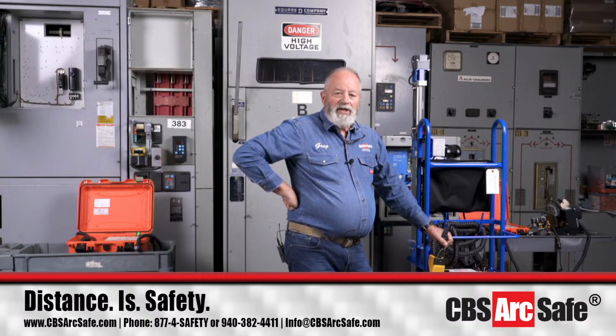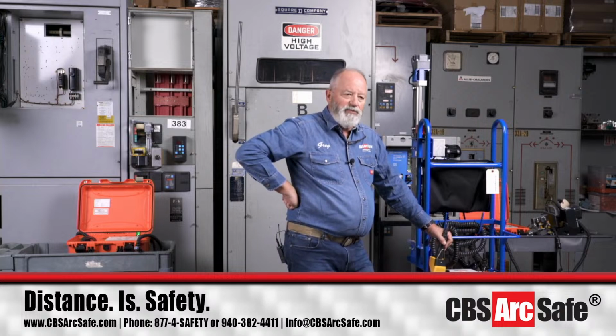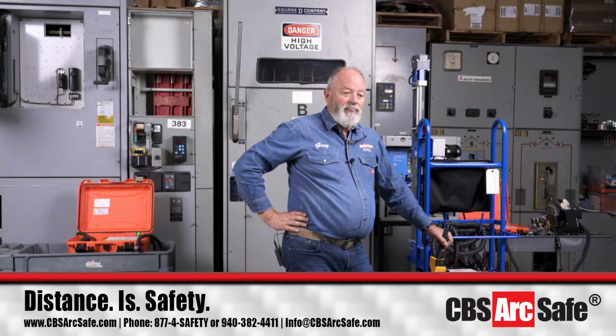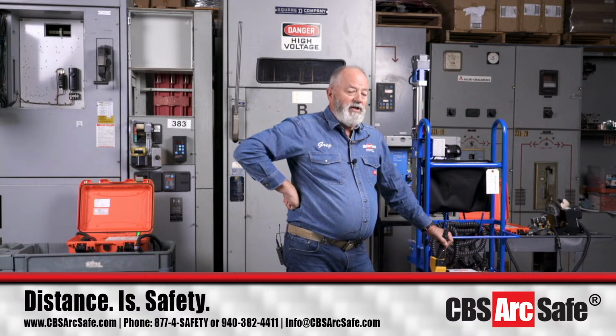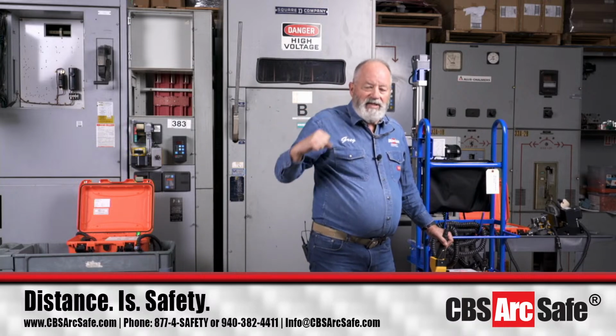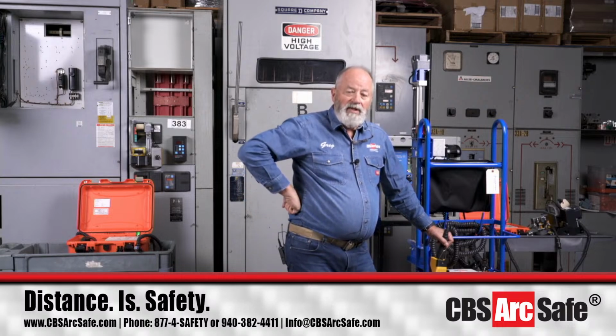And one of the things that I'm going to note right now is we also learn from our customers. So I was doing this the first year, and we went to one of our big customers in St. Louis, and they said, every time we rack this breaker in, we go back a half to a quarter of a turn from the full connected position. I asked the guy, why do you do that? And he says, because the racking mechanism and the operating mechanism are tied in together, and you can usually go a full turn to a turn and a quarter back, and the breaker is going to stay connected, the door is going to close for where the racking motor is, and the breaker is going to operate normally. And besides that, the next time you want to rack it out, you're not fighting the big guy who's left this thing all tightened up, and it actually does damage to the breaker if you do stuff like that. And we go, oh. So we learned that from a customer in St. Louis, and we work to share that with you.